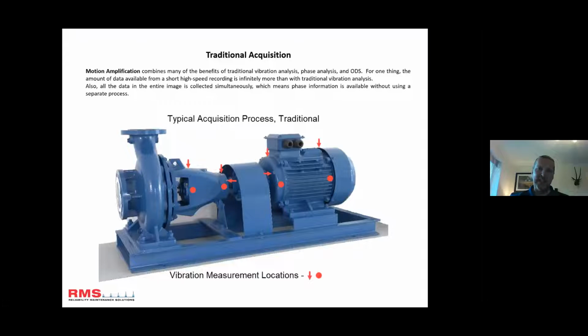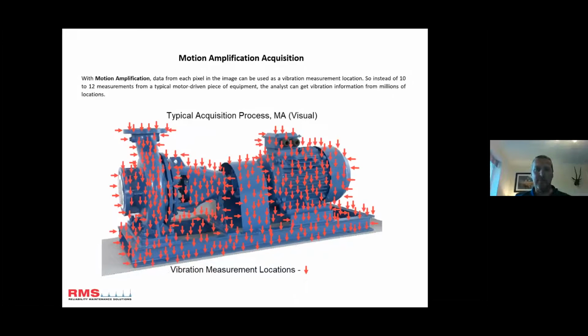Traditionally here we can see a picture of a pump, and this is where you'd normally take measurements using a traditional vibration system. This technology is not meant to replace traditional vibration by any means. It actually works really well with it, together they complement each other. So that's traditional vibration, and then we've got MA.